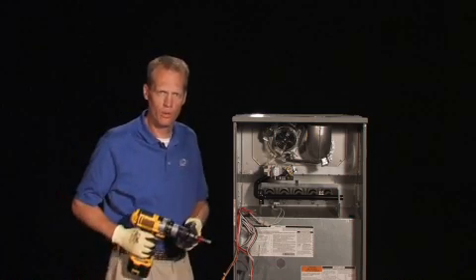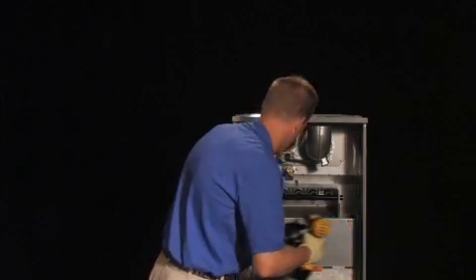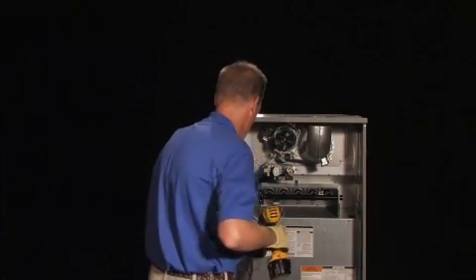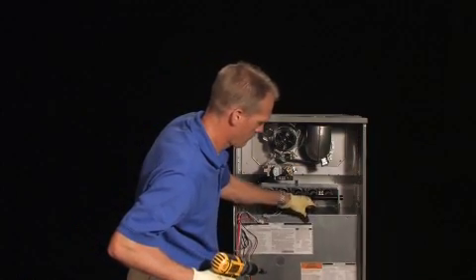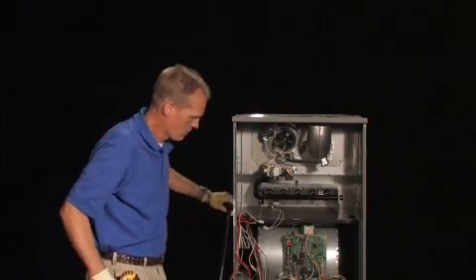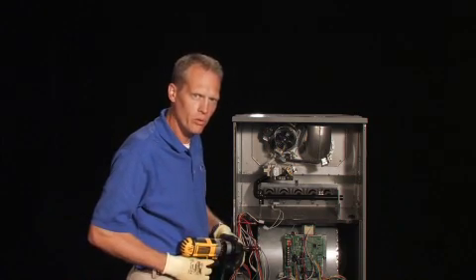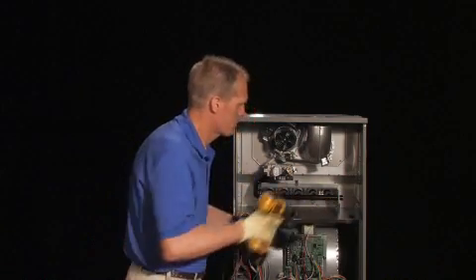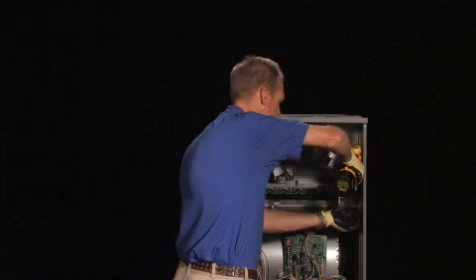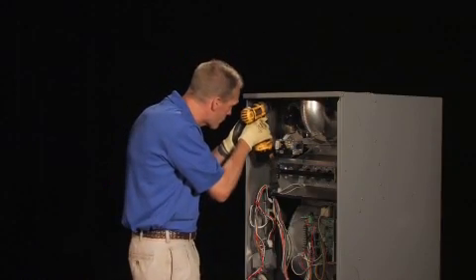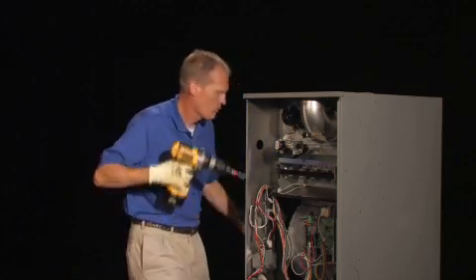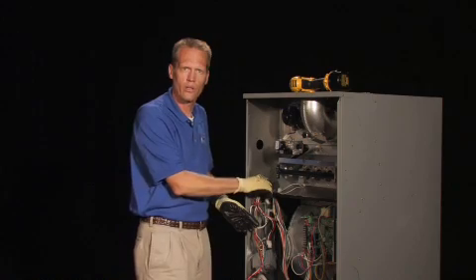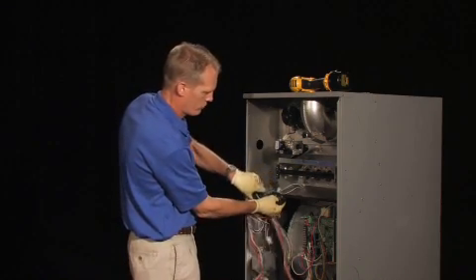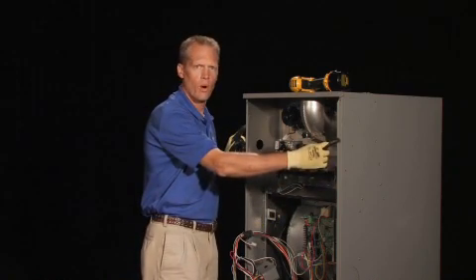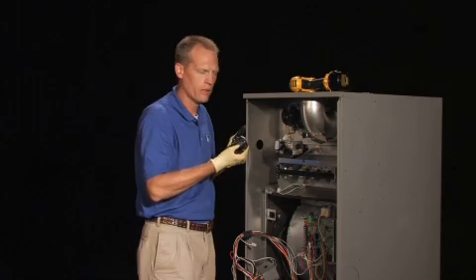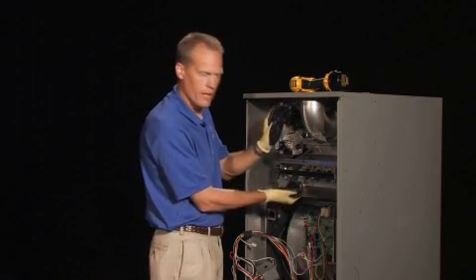Next, we need to remove the blower door. And then we remove the screws at the perimeter of the heat exchanger. I'll remove the last screw. Disconnect the wire harness from the panel. And the cabinet is wide enough for the entire assembly to come out the front. To do that, we'll tilt the top down and then slide it forward.